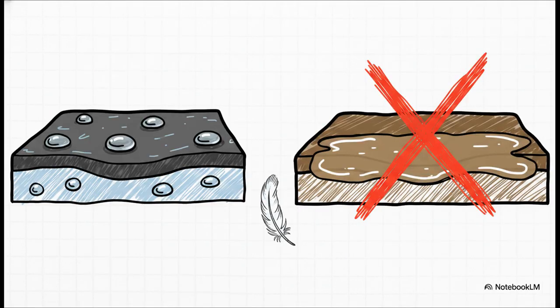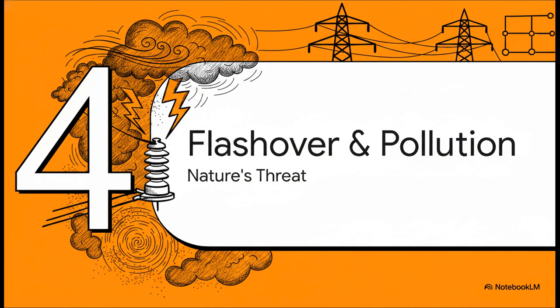We aren't just relying on old-school ceramics and glass anymore, though. Today, engineers also use modern rubber and polymer alternatives. Built from reinforced plastics and silicone rubber, these composite insulators are a fraction of the weight of their glass and porcelain cousins. But their true magic lies in their surface chemistry. They have this amazing, innate ability to make water bead up into separate little droplets. This stops moisture from spreading out into a continuous, unbroken sheet of water. And that is absolutely critical, because a continuous sheet of dirty water is the perfect bridge for electricity to escape. Let's look deeper at that in Section 4, flashover and pollution effects.